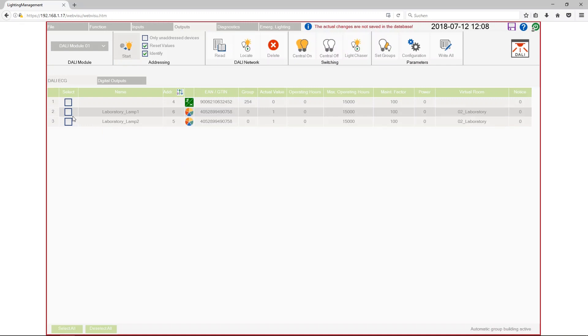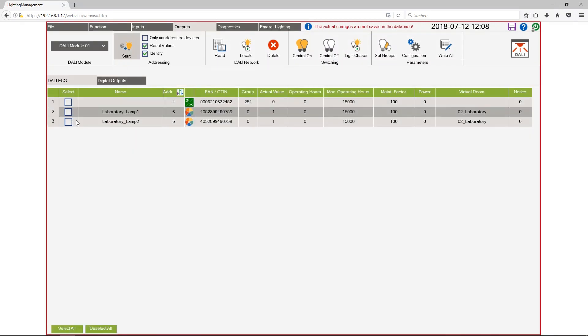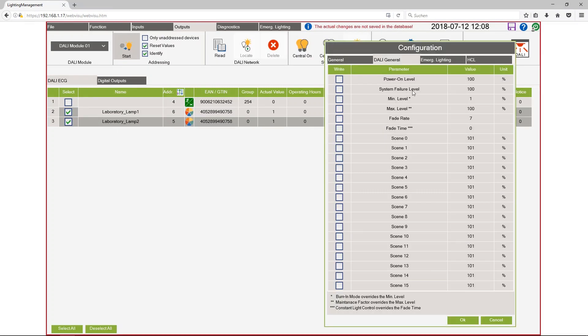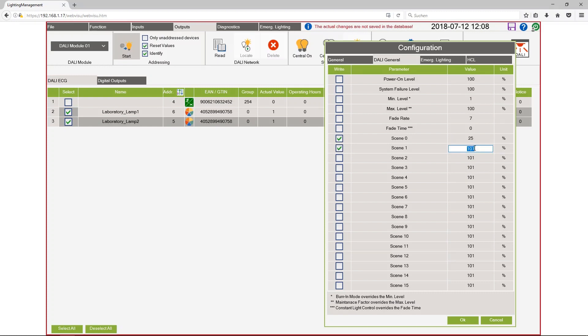And I want to configure also the scenes. So I select these two lamps again. Click on configuration and can configure in DALI general the brightness value for the first and the second scene. So I will configure 25% and 75% as a dim value.